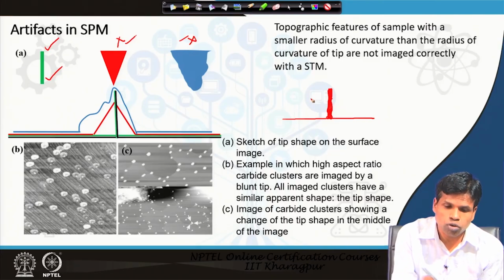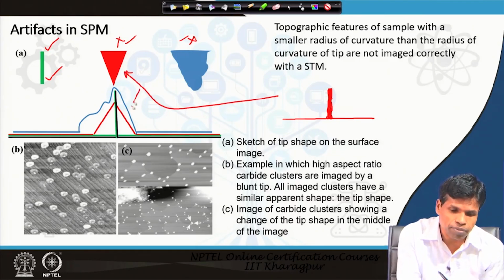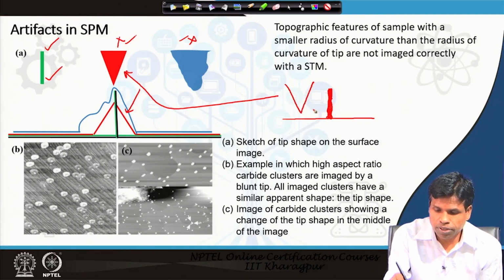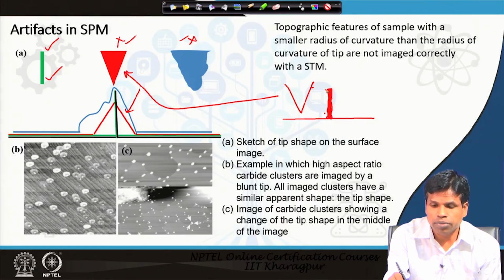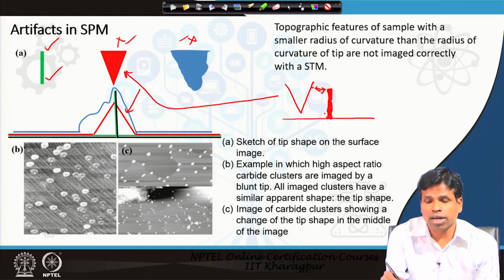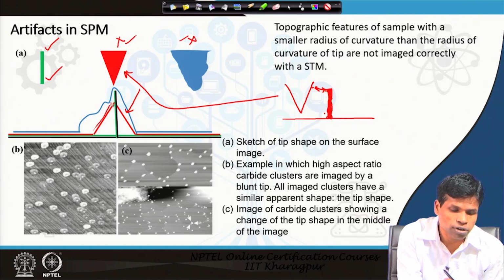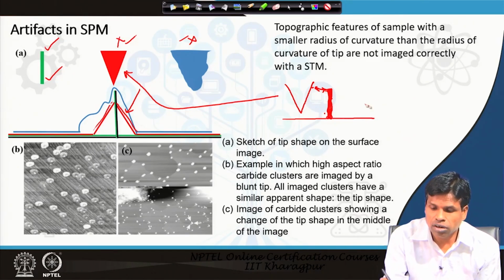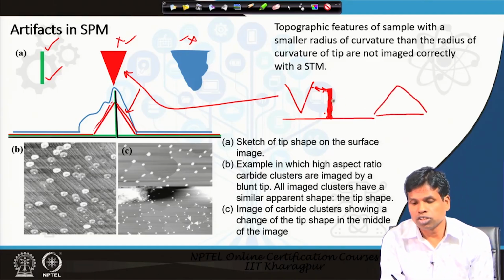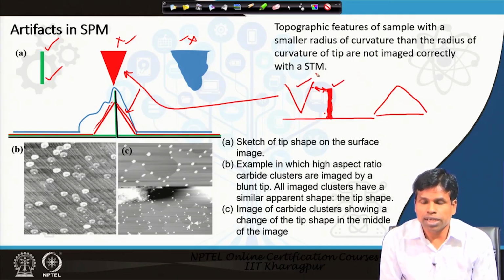On the other hand, if the same one-dimensional feature is seen by this type of tip, then we will get an image like this, because as soon as the tip comes closer, it cannot come very close, because this region will measure current. As we provide constant current mode for an unknown sample, it will make the tip go away from the sample, because at these places it will see a larger current, and therefore it will not allow the tip to come close to the one-dimensional feature. Therefore, the tip has to go above or away from the sample, providing an image like this. Even though the original feature is one-dimensional, using a triangular tip like this, we would get triangular features in the image.